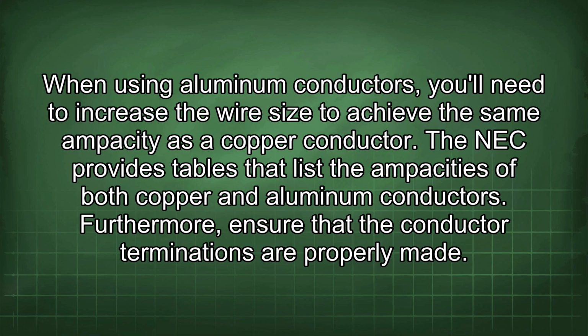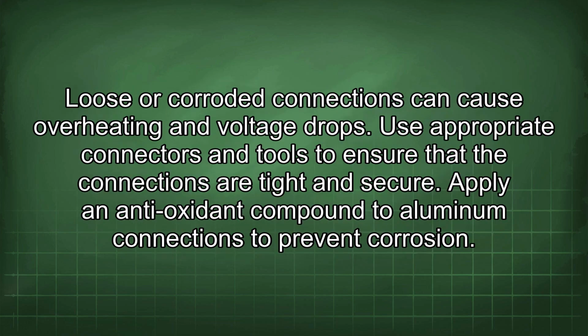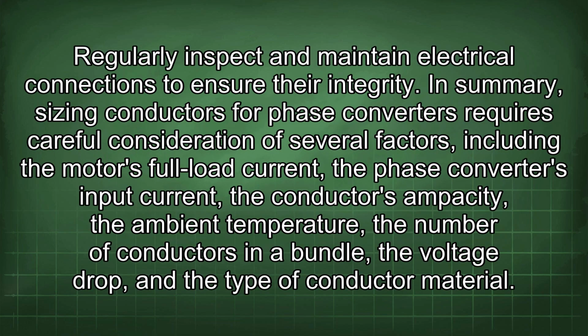Furthermore, ensure that the conductor terminations are properly made. Loose or corroded connections can cause overheating and voltage drops. Use appropriate connectors and tools to ensure that the connections are tight and secure. Apply an antioxidant compound to aluminum connections to prevent corrosion. Regularly inspect and maintain electrical connections to ensure their integrity.